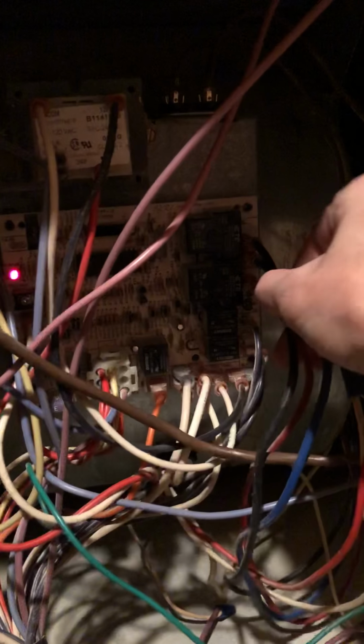Your main input power is down here. That goes to the transformer, goes to everything else. Then I checked the motor coils. I took off, here's 3 different speeds of the motor. And this is the common for the motor. It's grounded on the outside of the chassis. So you've got this one, black is high. It's the high speed of the motor. Blue's medium speed. Red's low speed. I've got a 3-speed motor.